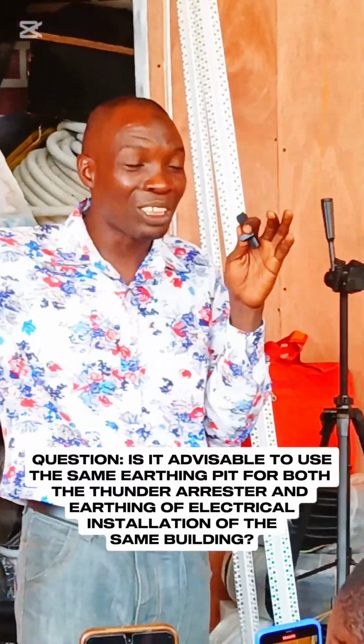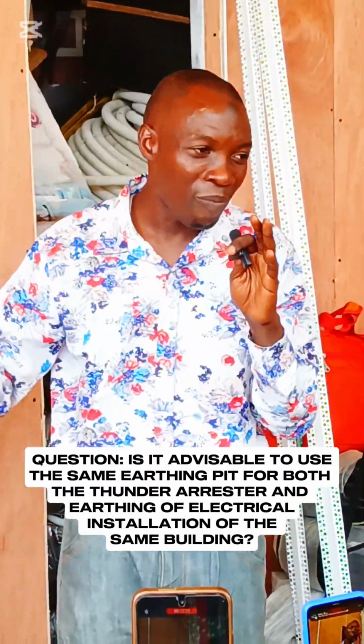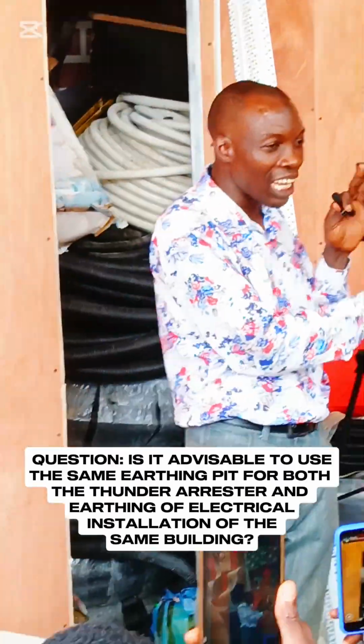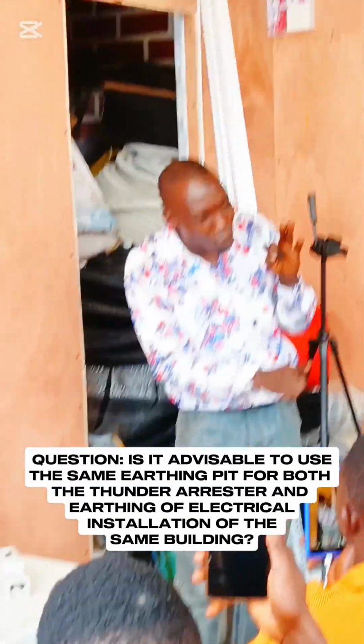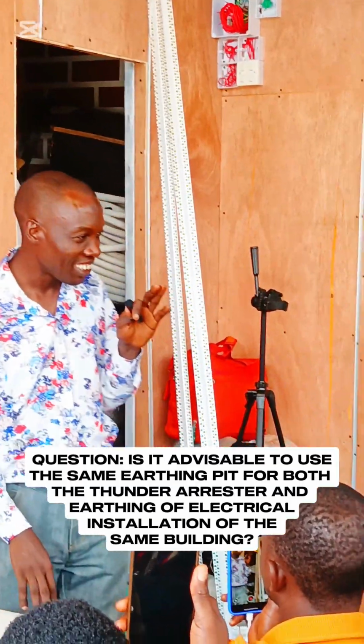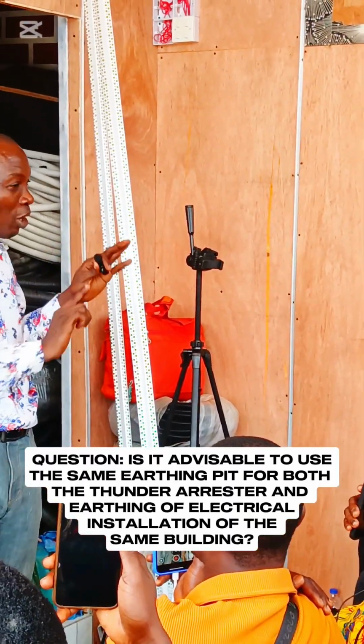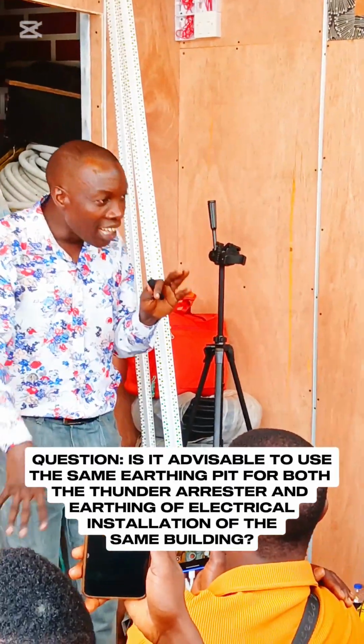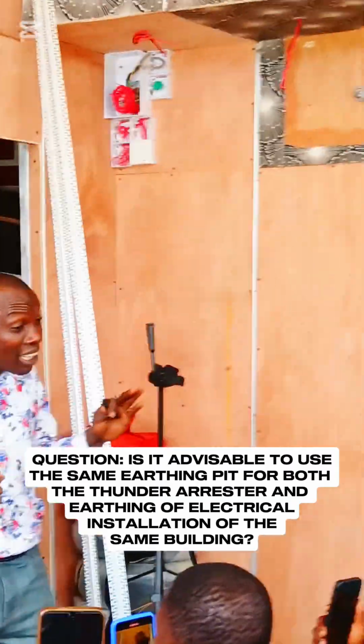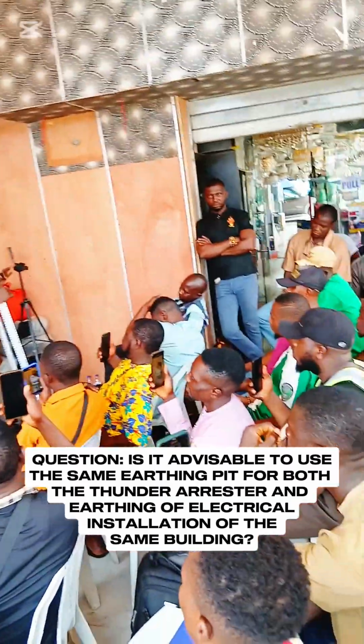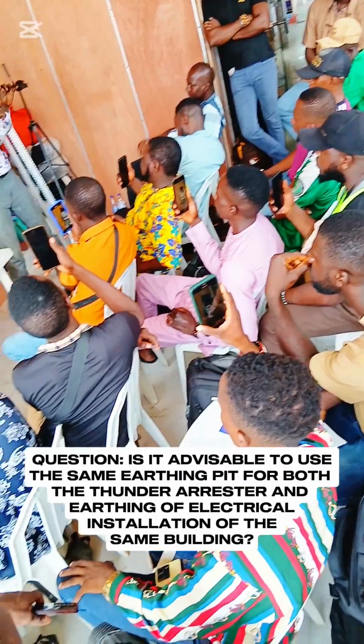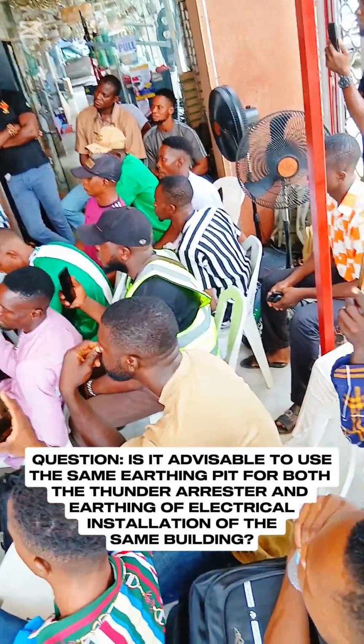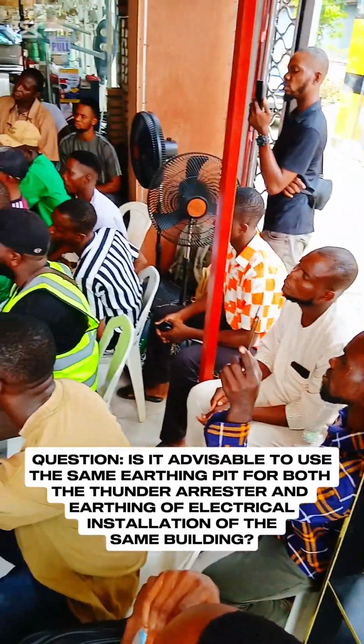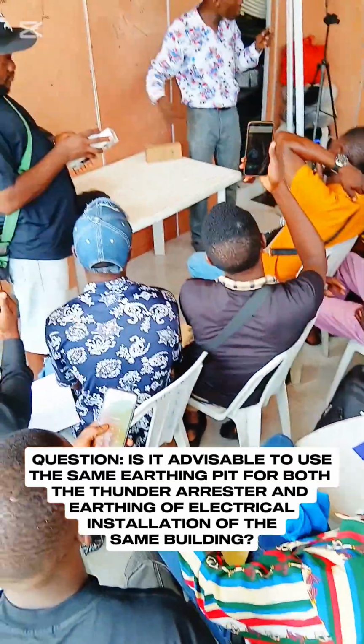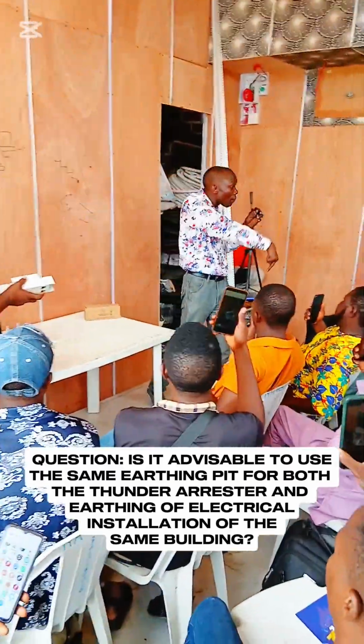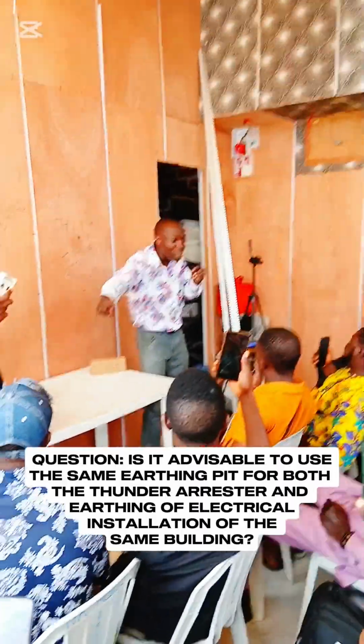In electrical engineering, we believe there is what we call earth fault loop. Anytime there is a fault in an installation, you create a path for that current to flow away and back to the supply transformer. When they want to install a transformer, they normally ground it, and the earthing is very effective, very active. So it is to create a low resistance path, because the supply transformer remains the source from which all other residences connect their supply. So if the fault comes from your own, it has to return to that path, because there must be a complete path for that fault loop.